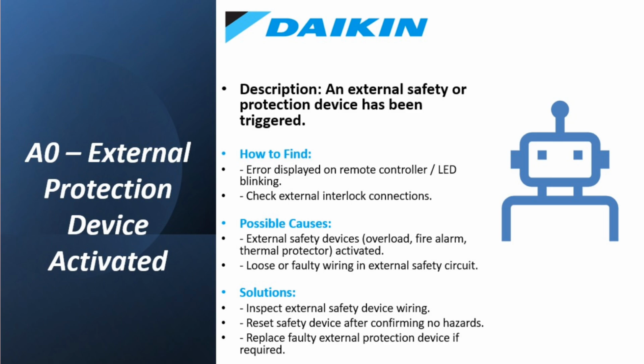External protection device activated. This just means an external safety device, like a fire alarm or overload protector, has been triggered. Check your wiring and reset the safety device only after making sure there's no real danger. If the device keeps tripping, you might need to replace it.